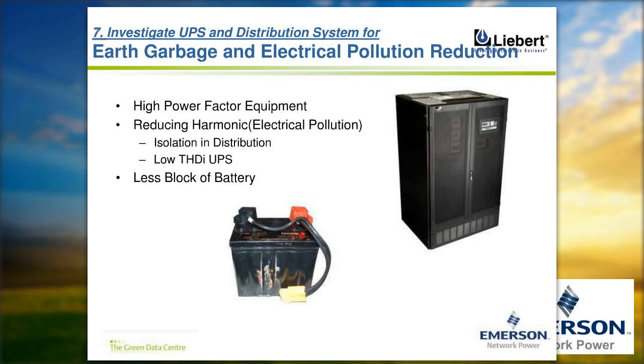Okay, we do have a lot of electrical pollution happening inside data centers because of harmonic distortions, total harmonic current factors and batteries also. That needs to be handled. We recommend using transient voltage surge suppression, which can take care of all the transients generated from the switching of loads or passed on from sources which may impact the operations of any equipment.